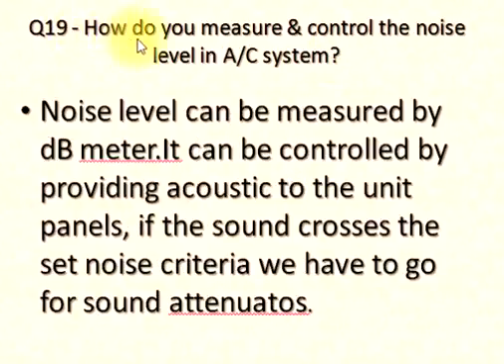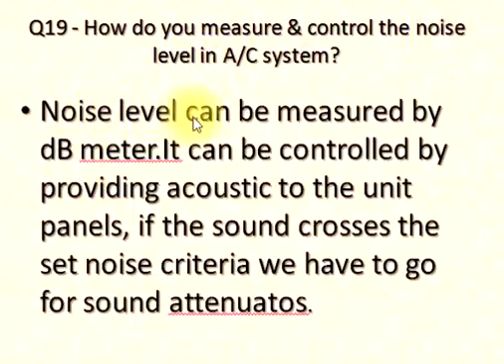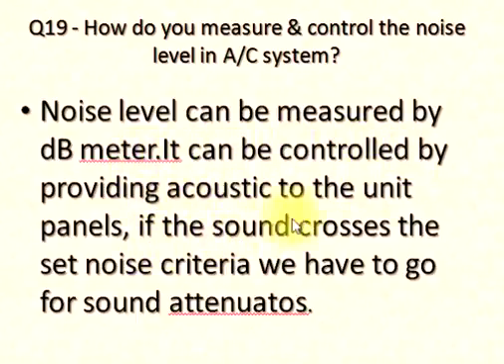Q19: How do you measure and control the noise level in an AC system? Noise level can be measured by a dB meter. It can be controlled by providing acoustic treatment to the unit panels. If the sound crosses the set noise criteria, we have to go for sound attenuators.